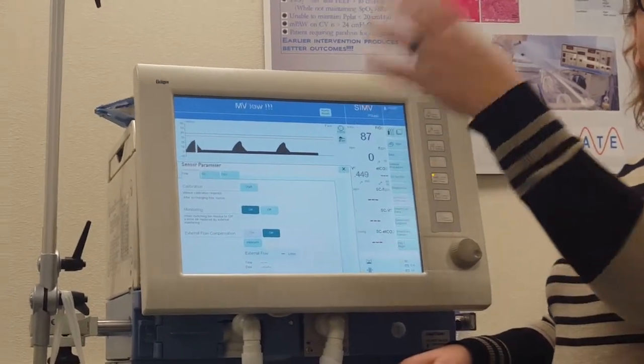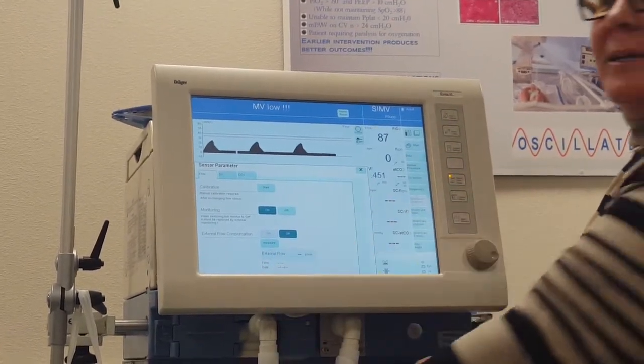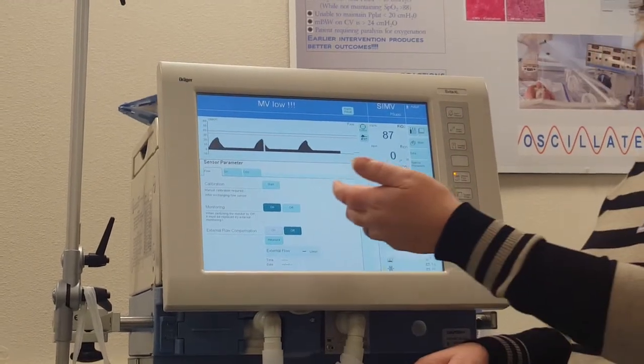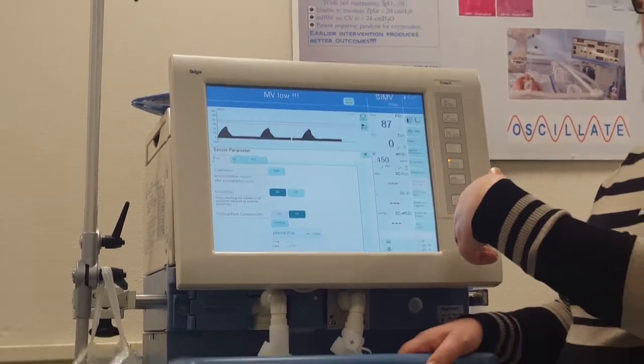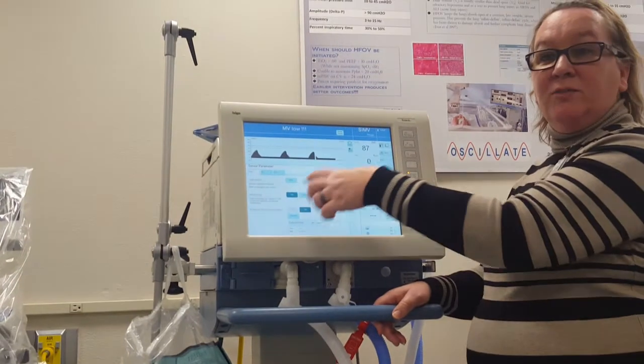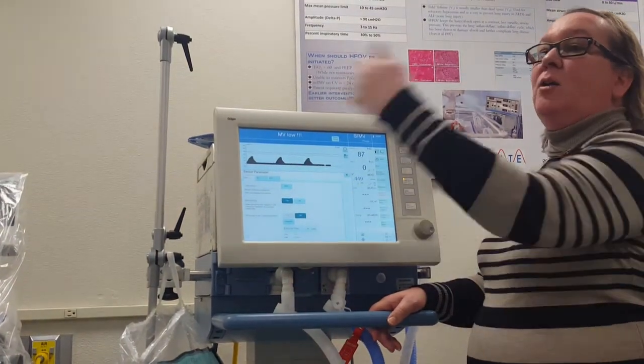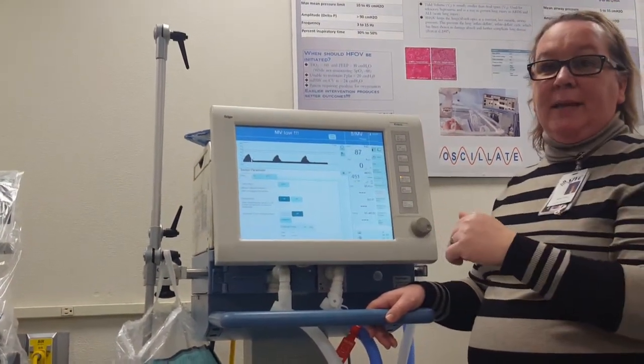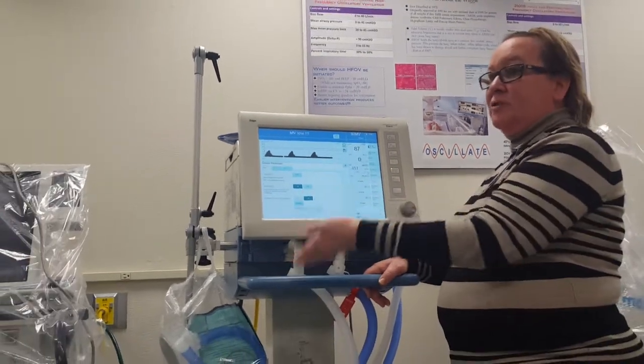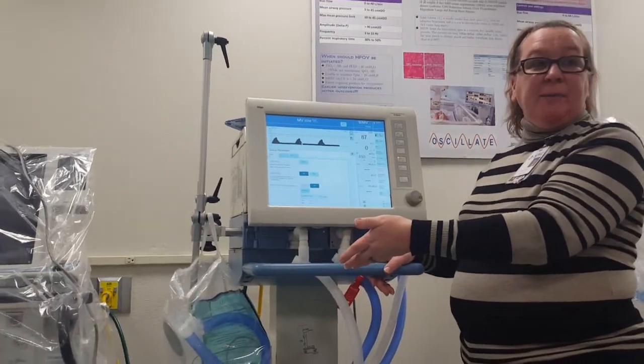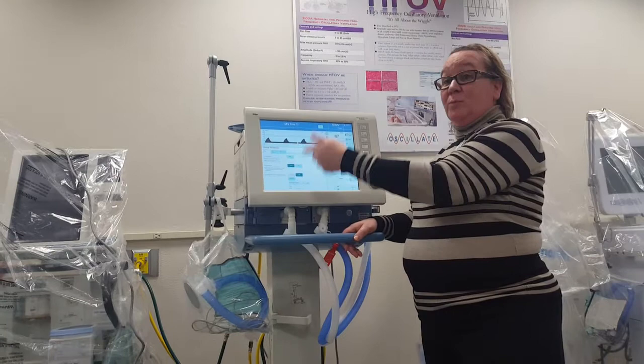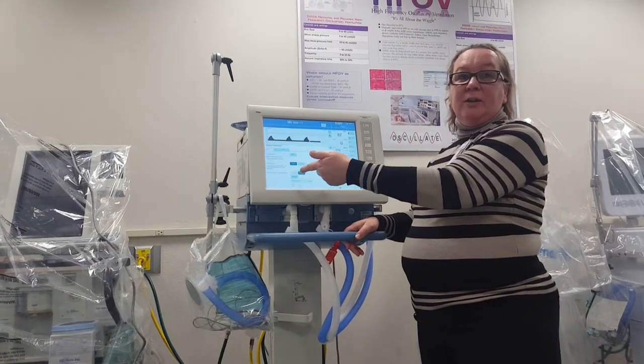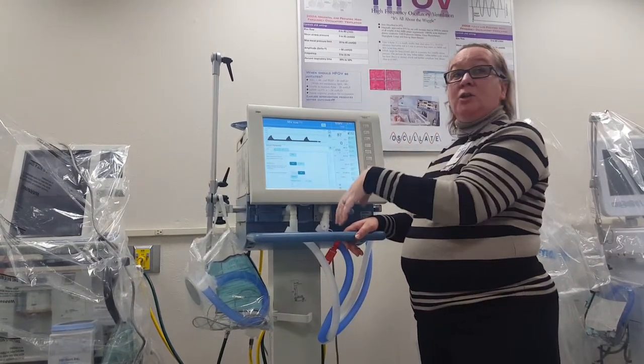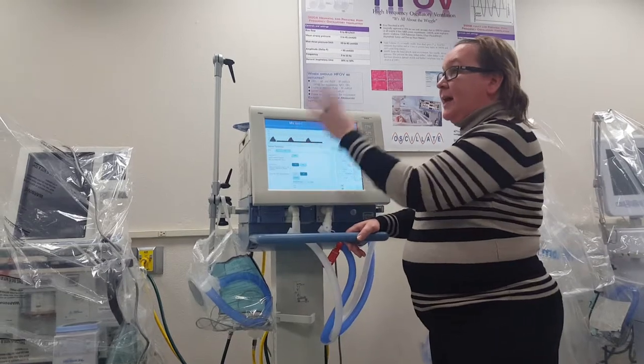So let's say we bag our patient and get a new flow sensor, because I can just replace the flow sensor and everything should be fine. And I need to calibrate it again though. Then you can just go here and do just a flow sensor calibration, and you don't have to do that whole device check like we did in the beginning. Flow sensor on the DRAGER is a very common piece that has to be replaced. If you replace it, you need to recalibrate it. So that's how you can do that very quickly. Someone's bagging your patient, get a new flow sensor, put it in, recalibrate it, and you're done.